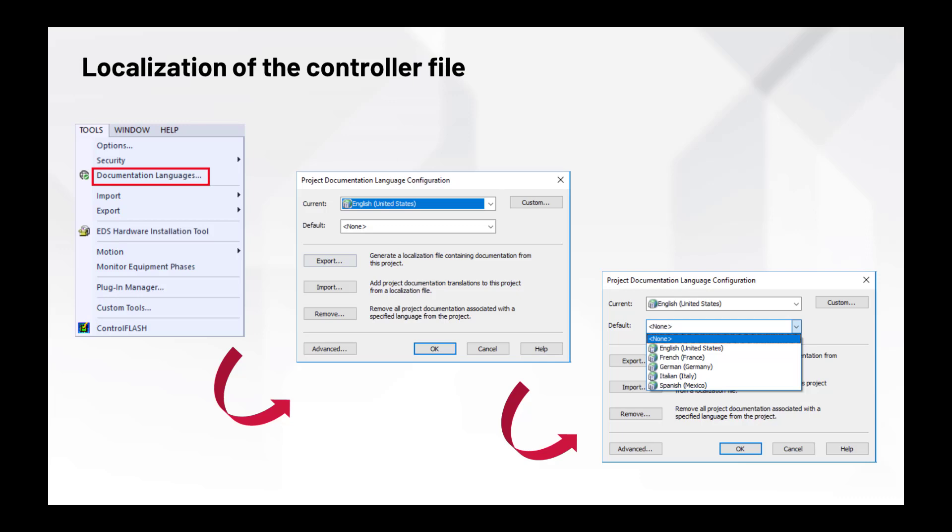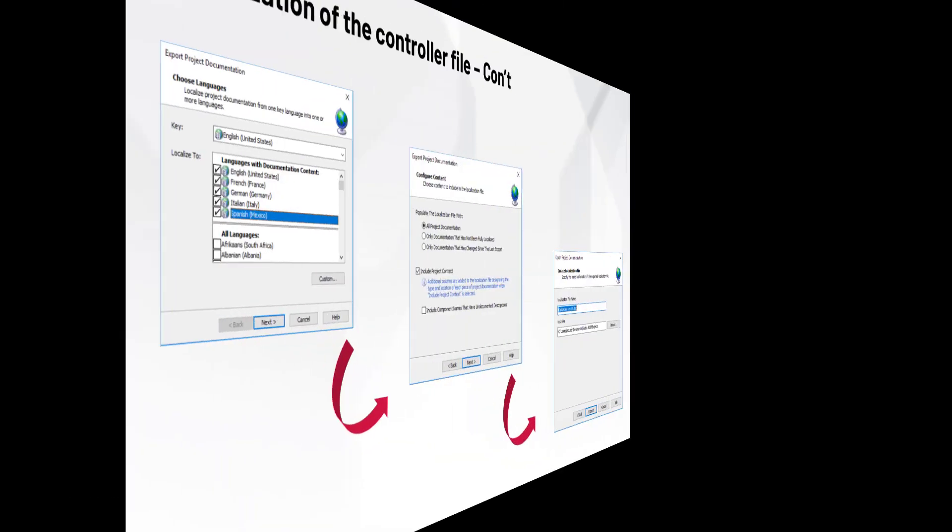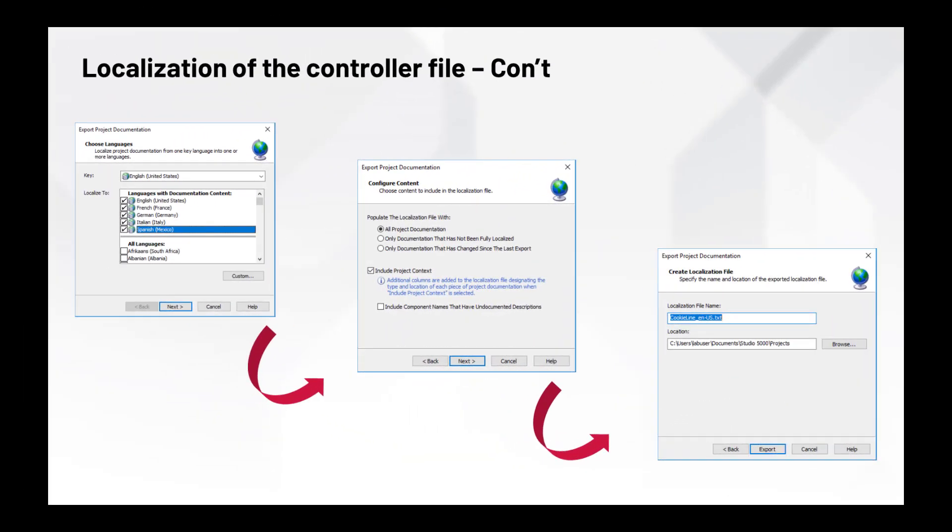Now let's take a quick look at the process used to incorporate different languages into Studio 5000 Logix Designer in order to perform language switching using extended tag properties. Under the Tools menu in Studio 5000 Logix Designer, select the Documentation Languages option. This option provides the ability to localize the controller file. The first step in the process is to associate existing project documentation to a language. Next, a default language for the controller must be defined. This is the language that will be used when no translated text is specified for a specific language. At this point, the languages are then selected for localization. These must match the languages configured within the FactoryTalk View Machine Edition application.